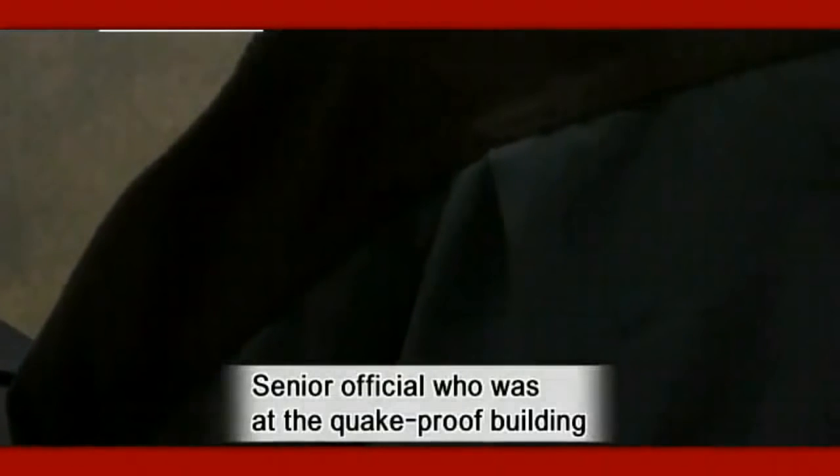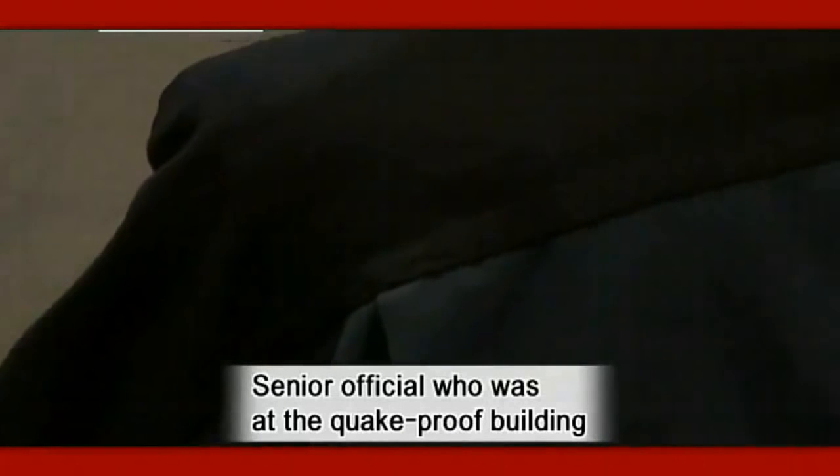Why didn't TEPCO officials realize it? We discovered that Tepco had not activated the isolation condensers in Reactor 1 for about 40 years. None of the operations staff had ever seen what kind of steam the condensers discharge when they're turned on. I had never seen a working condenser. Any steam discharge was taken as an affirmation that the condensers were active. No one declared that they were idle. I guess we were unable to provide the kind of information to plant managers that would have pushed them to do something.